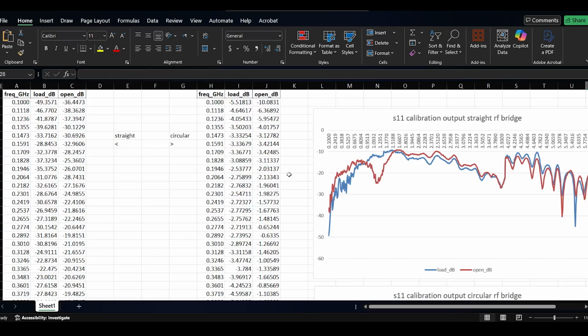Plus, one other issue that I talked about earlier in the video is that the directivity of the balun is definitely not ideal, and sometimes you can measure the amplitude when the load is connected to be higher than the open, due to some of the leakage that is getting back from the RF output port to the bridge, right? You can see, for the straight RF bridge, this is happening at around 1 gigahertz and then 1.5, meaning that if this is the open, the amplitude measured when calibrating with open and load, the open amplitude becomes much smaller compared to the load, right? And this is not something we want. So this shows that this RF bridge is not acting well in this frequency region.